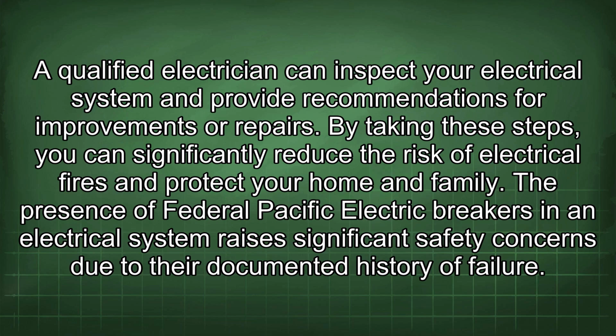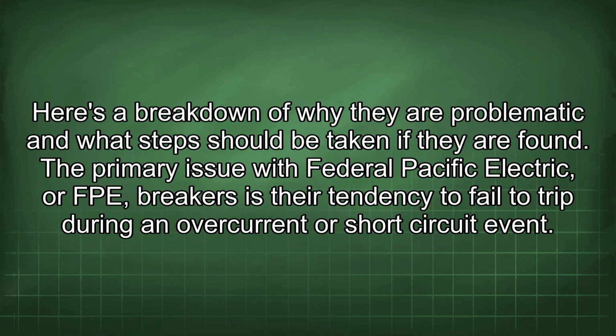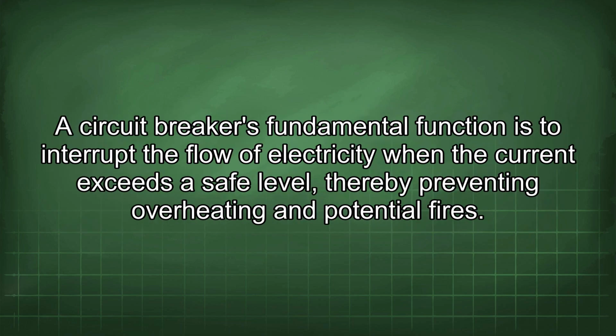The presence of Federal Pacific Electric breakers in an electrical system raises significant safety concerns due to their documented history of failure. Here's a breakdown of why they are problematic and what steps should be taken if they are found. The primary issue with Federal Pacific Electric, or FPE, breakers is their tendency to fail to trip during an overcurrent or short circuit event. A circuit breaker's fundamental function is to interrupt the flow of electricity when the current exceeds a safe level, thereby preventing overheating and potential fires.